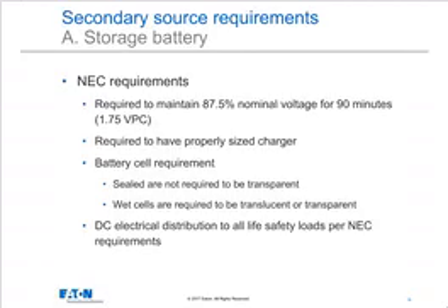The storage battery alone, the NEC requires that the battery lasts for 90 minutes. That's a lot longer than we're used to in UPS applications. So at least an hour and a half. There's a few cities that still require even longer than that as a part of the local code. The battery is required to have a properly sized charger. What is that? It means it can't take 2 weeks to recharge that battery. Typically, they're going to be looking for about a 48-hour recharge time, at least, on a 90-minute battery.